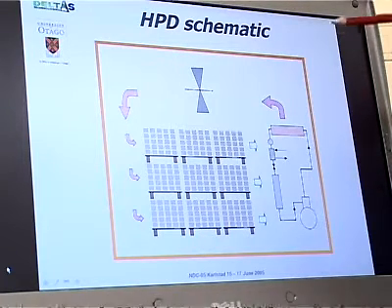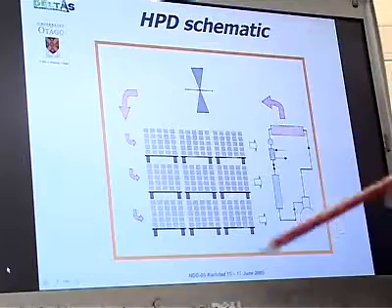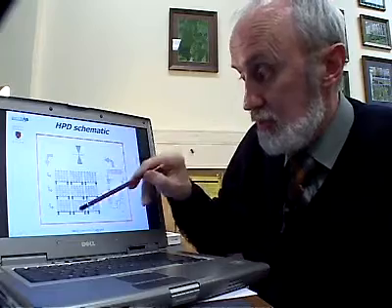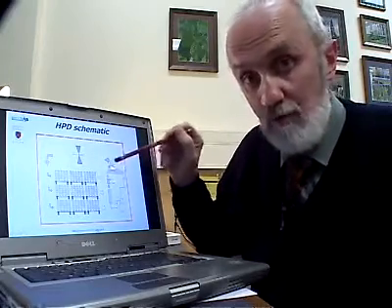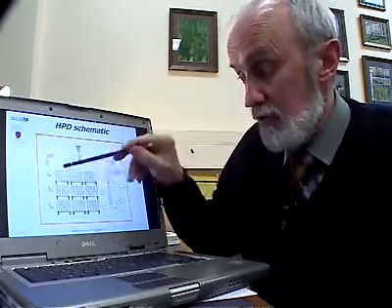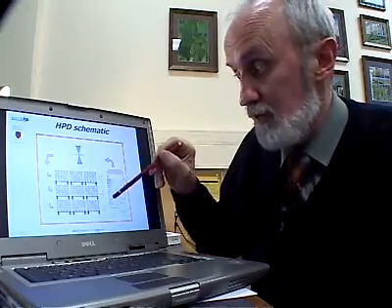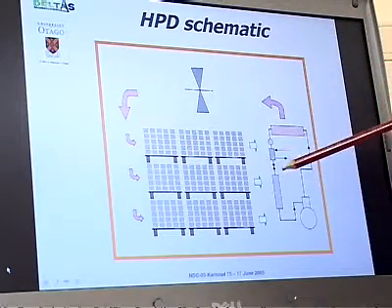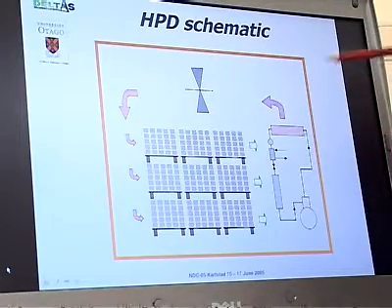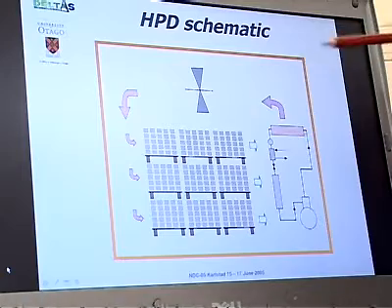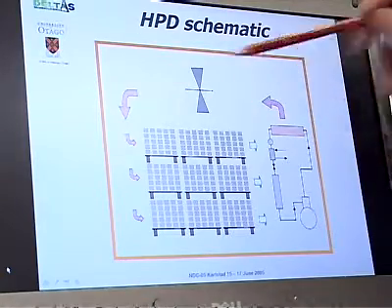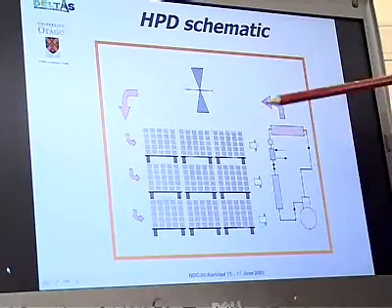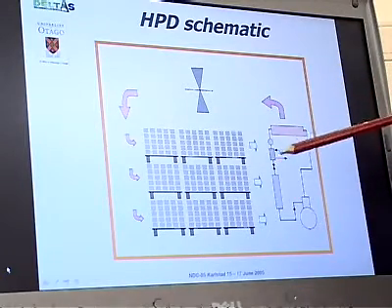Well, this shows a schematic of the kiln with the heat pump dryer in it. And just showing schematically, this is the load of timber. The load of timber can be quite large, perhaps about 50 cubic meters, so this actually is quite a large piece of a stack of timber. And there's a fan up here that moves the air around through the timber, through the dryer, and round again. One of the features of the dryer that we are responsible for is the ability for this to go backwards as well as forwards, which means that you dry the timber more evenly and as a result more quickly.